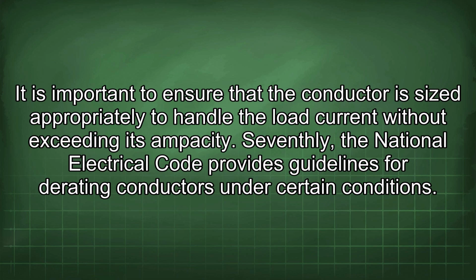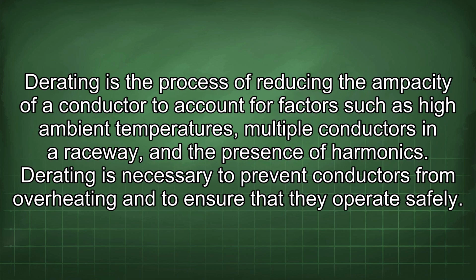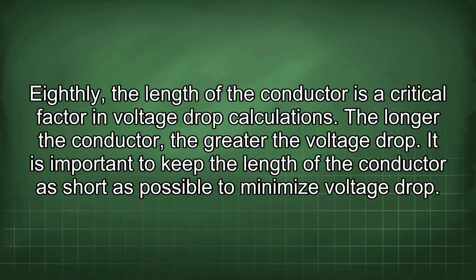Seventhly, the National Electrical Code provides guidelines for derating conductors under certain conditions. Derating is the process of reducing the ampacity of a conductor to account for factors such as high ambient temperatures, multiple conductors in a raceway, and the presence of harmonics. Derating is necessary to prevent conductors from overheating and to ensure that they operate safely. Eighthly, the length of the conductor is a critical factor in voltage drop calculations. The longer the conductor, the greater the voltage drop.